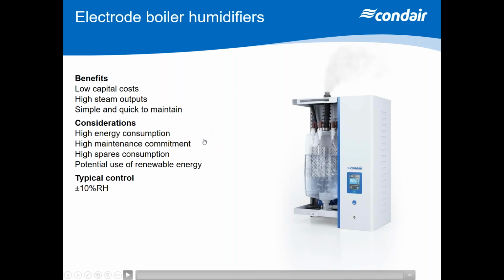But you are going to be using electrical power. So again, for every 100 kilograms of steam, 75 kilowatts. There's a high maintenance commitment. And again, that is down to the water quality. You've got to change the cylinder. You've got to clear out the drain pump. That's something that's got to be allowed for in a maintenance regime. And of course, you've got to pay for the replacement spares.